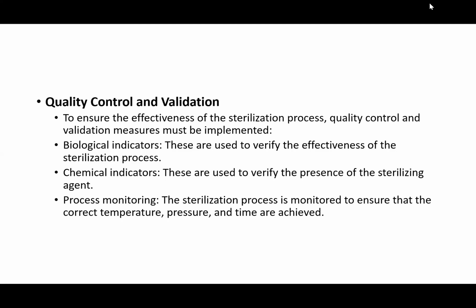Now, there are biological indicators. Now, you should know some of these indicators are used to monitor or verify the effectiveness of the sterilization process itself, while some verify the sterilizing agents, then you also monitor the process. These are the three processes that are involved in quality control and validation. Now, biological indicators are used to verify effectiveness of sterilization process. Then chemical indicators are used to verify presence of sterilizing agent. Then the process monitoring. The sterilization process is monitored to ensure that the correct temperature, pressure, and time are achieved.